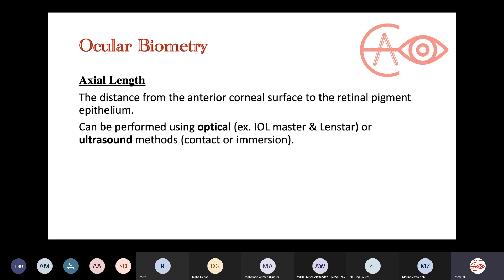The next component is the axial length, measured from the anterior corneal surface to the RPE. There are two ways to measure it: using light waves — optical measurement — or sound waves — ultrasound. For optical measurement, the devices are the IOL Master and Lenstar, which use light waves to give accurate measurements.